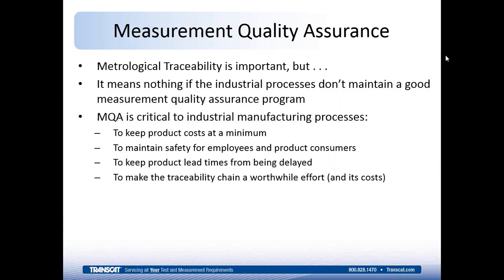And in the end, we have this calibration traceability chain that has a lot of expense to it, all the way from the National Measurement Institutes around the world to the secondary labs and calibration labs that are used to calibrate product lines. All of that cost is a waste if, in the end, the instrument isn't used right or the wrong instrument is used for the job to get the job done.